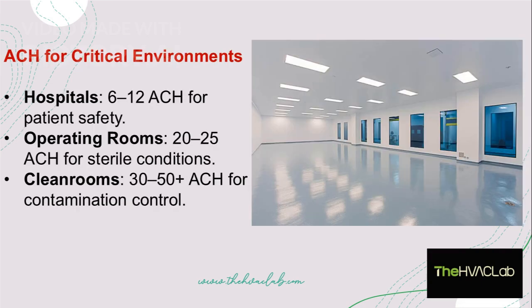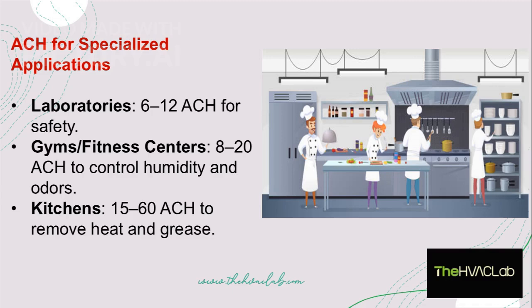Hospitals need 6 to 12 ACH for patient safety. Operating rooms require 20 to 25 ACH for sterile conditions, and clean rooms need 30 to 50 ACH for contamination control.